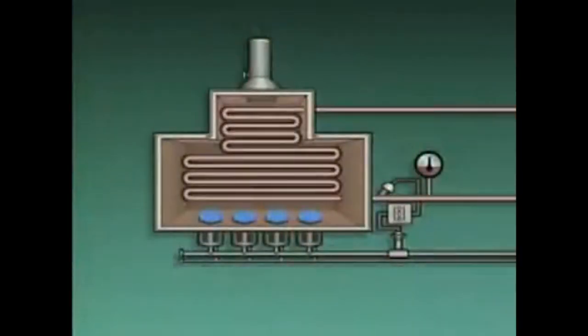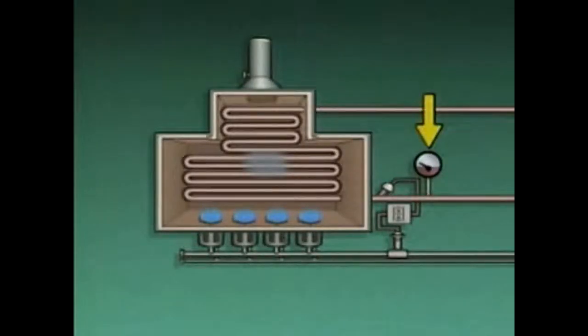A potentially dangerous airflow problem is insufficient airflow at the burners. If there's not enough air at the burners, some of the fuel sent to the furnace may not get burned. With unburned fuel in the furnace, you may notice that the firebox is hazy. Also, since the fuel is not burning completely, the outlet temperature of the process fluid could go down. If the outlet temperature goes down, the outlet temperature controller will trigger an increase in fuel flow to the burners, but this only aggravates the problem. If this extra fuel doesn't get burned, the outlet temperature is going to keep dropping.